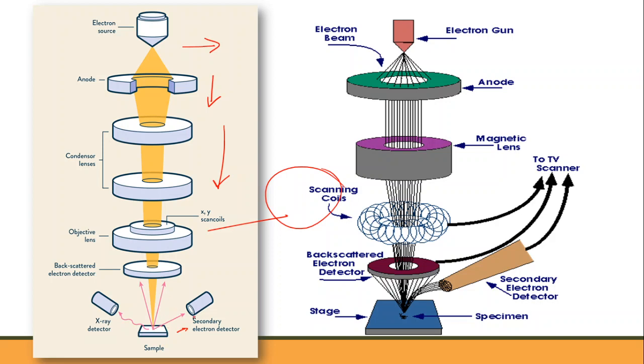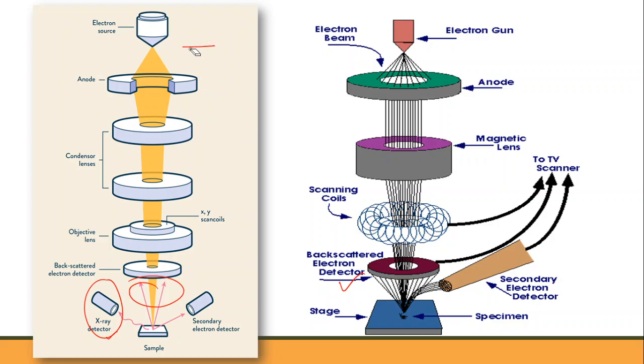When the electron beam touches the surface of the sample, it produces secondary electrons — electrons released from the sample surface. Electrons can also come back as backscattered electrons, or energy may be emitted as X-rays. The secondary electron detector collects these emitted secondary electrons, converts them into a signal, and sends it to the screen to produce the final image. Additional detectors for backscattered electrons and X-rays can also be placed.